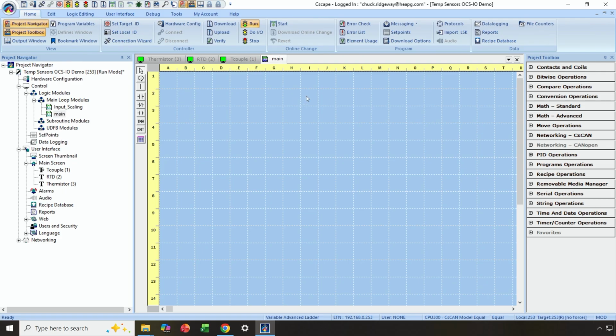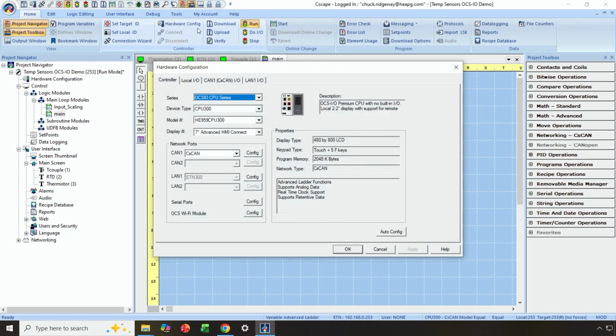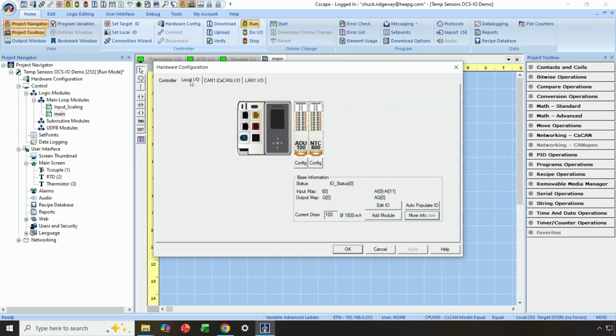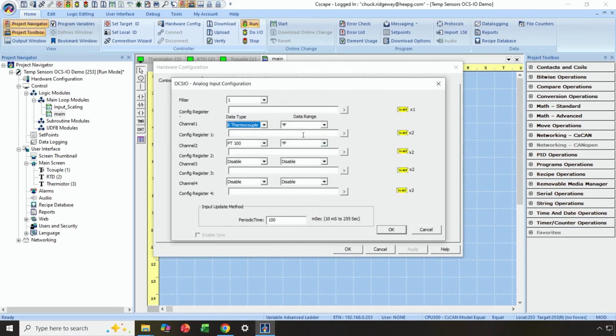All right, so this is my ladder area. I don't have any logic right now in this bench demonstration. I'm just directly showing the values on the screen. So let's go into hardware configuration and take a look at how things are configured. So here is my CPU 300. I go to the local I/O tab, and here you'll find my universal analog input module and my thermistor module. So let's double click on those and take a look at how they're configured.